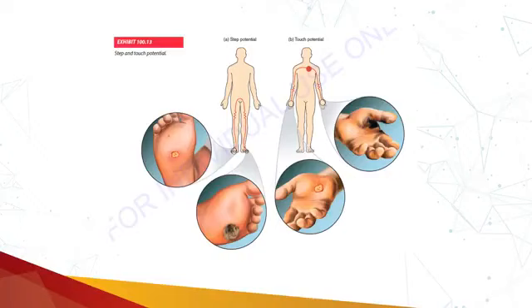If you are in such a close proximity, then it can cause you electric shock due to the arcing over phenomena. In the arcing over phenomena, basically the electrons jump through the insulation or the air gap and can cause you electric shock. So most electric shocks are defined in terms of step potential and touch potential. These are the definitions you are going to find in Article 100.